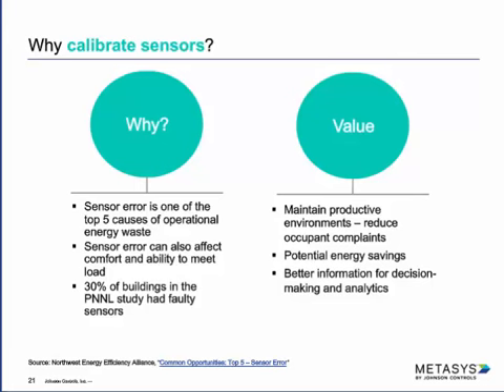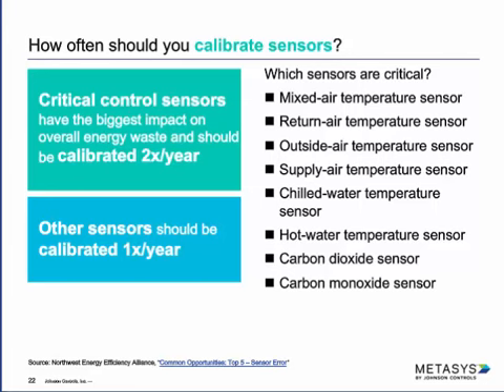Studies have shown that sensor error is one of the top five causes of operational energy waste, and it also affects comfort and the ability to meet load. In the PNNL study, 30% of buildings had issues with their sensors. We'll talk a little more about calibration and what you should be thinking about.